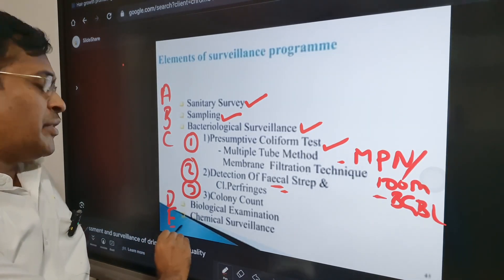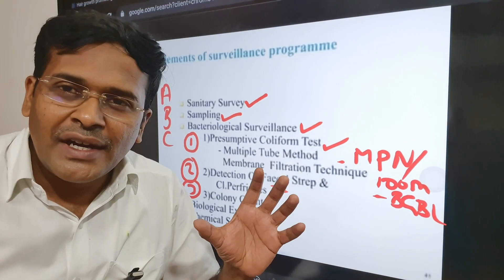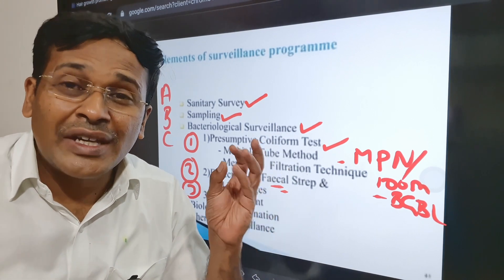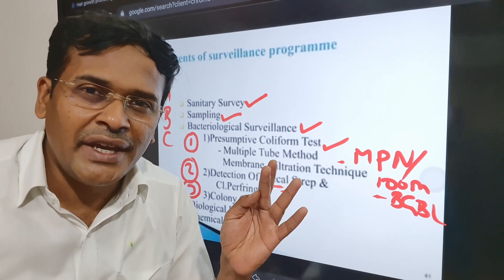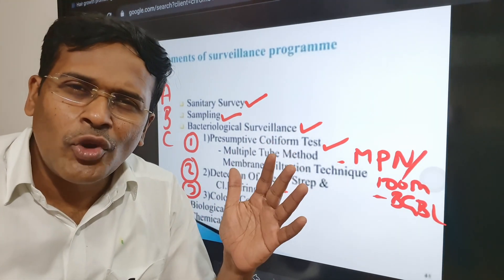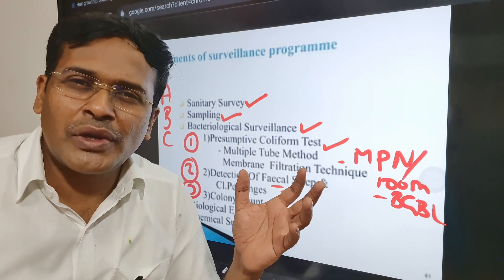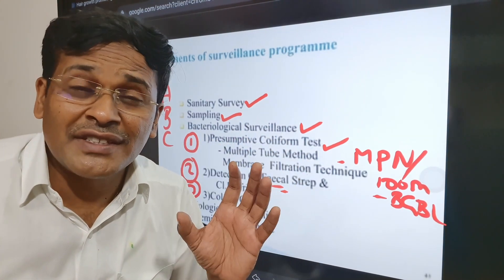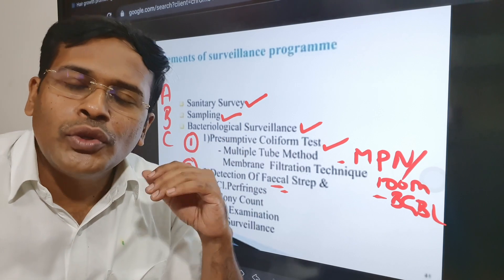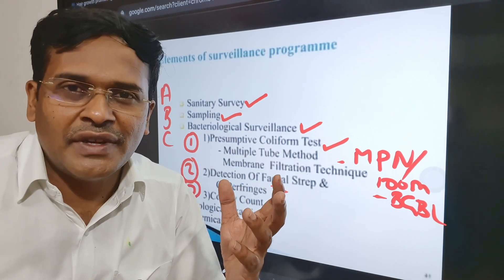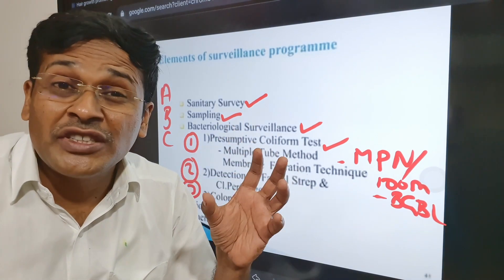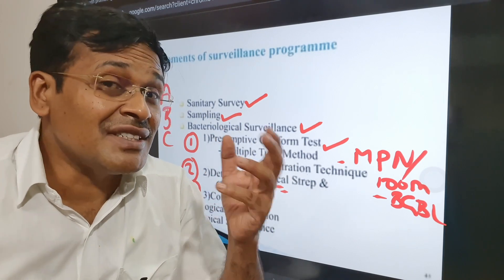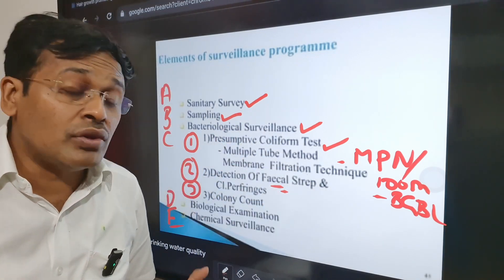The fifth point is chemical surveillance. A complete analysis of water chemicals includes pH, color, turbidity, chloride, ammonia, chlorine demand, and residual chlorine as basic tests. For intensive surveillance, you should also check for toxic metals, pesticides, persistent organic chemicals, and radioactivity in water.